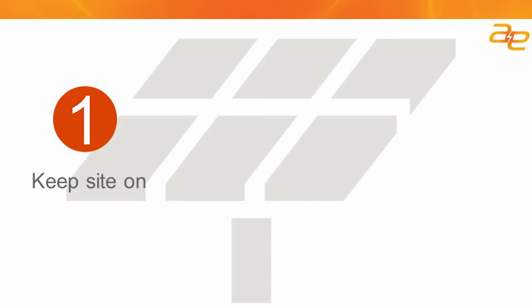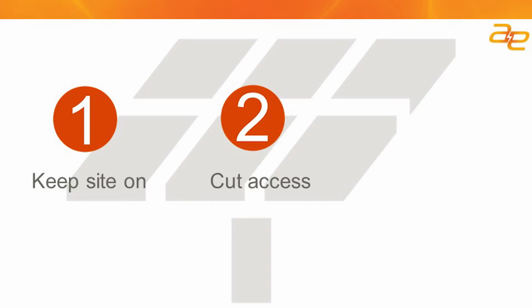So you can take a 100 megawatt site, command it to 50 megawatts relatively easily if the site has a control system. Or if there's too much generation and the sites don't have the ability to be curtailed, then they're just cut off completely. Somebody will open the 52 breaker at the site, whether it's the customer or the transmission operator, and just take the entire facility offline.